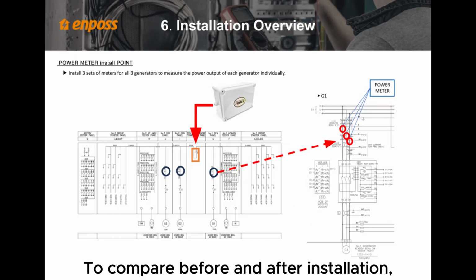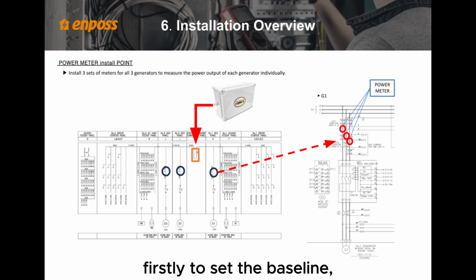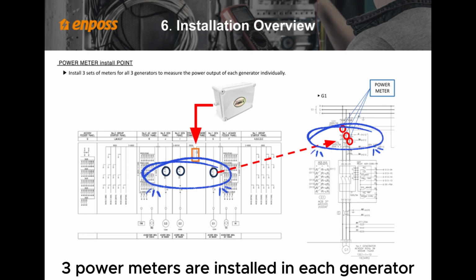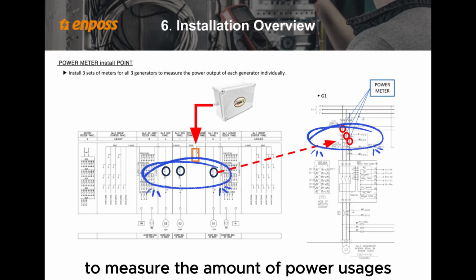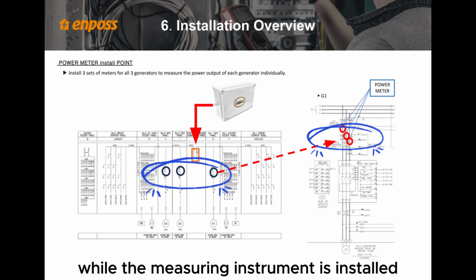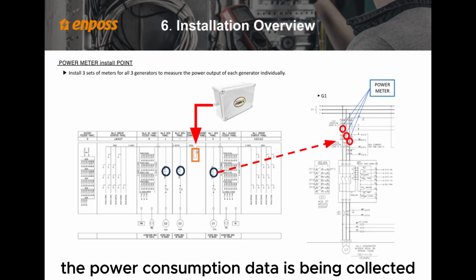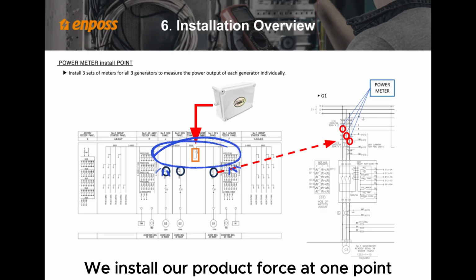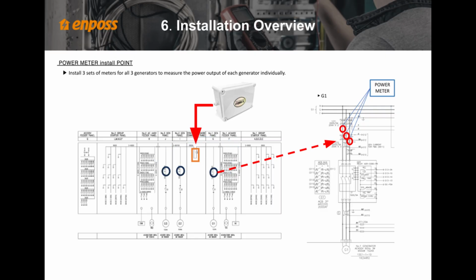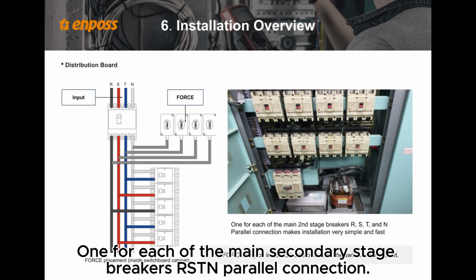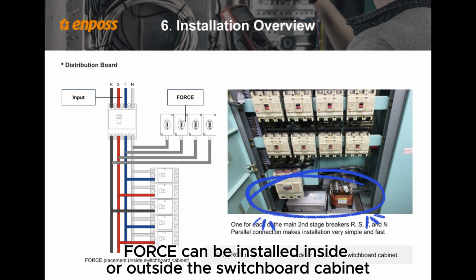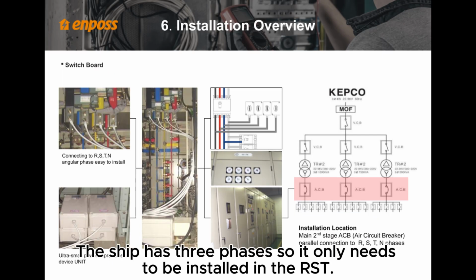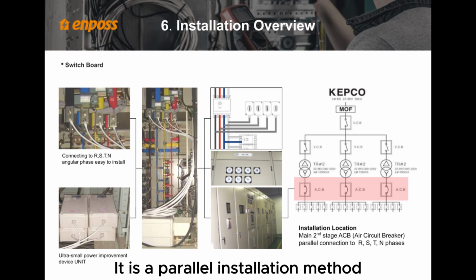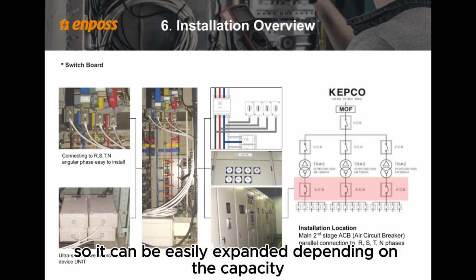To compare before and after installation, firstly, to set the baseline, 3 power meters are installed in each generator, as shown in the figure, to measure the amount of power usage. While the measuring instrument is installed and the power consumption data is being collected, we install our product Force at one point, as shown in the figure, after 1 or 2 voyages. One for each of the main secondary stage breakers RST, N parallel connection. Force can be installed inside or outside the switchboard cabinet. The ship has 3 phases, so it only needs to be installed in the RST. It is a parallel installation method, so it can be easily expanded depending on the capacity.